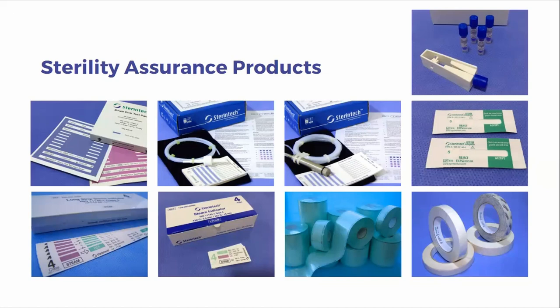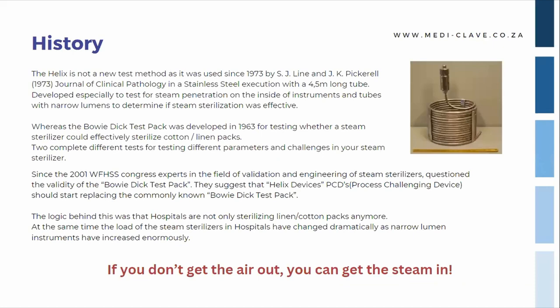So let's look at the history of sterility assurance products. The Helix is not a new test method, as it has been used since 1973 to test steam penetration on the inside of instruments and tubes. The Bowie-Dick test pack is also not a new test method. It was developed in 1963 for testing whether a steam sterilizer could effectively sterilize cotton or linen packs. Two very different tests for testing different parameters. Since 2001, at the WFHSS Congress, experts in the field of validation and engineering of steam sterilizers have questioned the validity of Bowie-Dick test packs. They suggested that the Helix device, the PCD, or process challenge device, should start replacing the commonly known Bowie-Dick test pack.